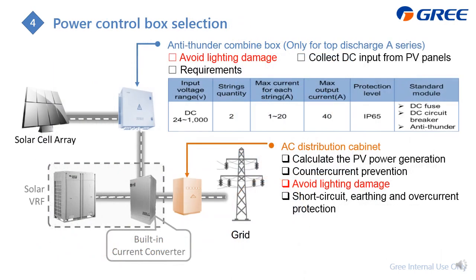And next is how to do the wiring from the PV panels or from the grid power supply to the PV GMV, which is this one. From here you can find that we separate the power from the PV panels, and this is only for the A series as we don't have the converter, so we need to set up another converter. The purpose of this one is just to avoid the lightning damage.